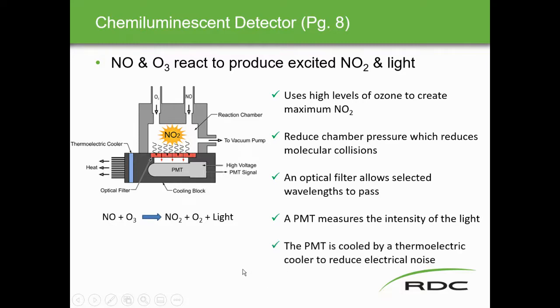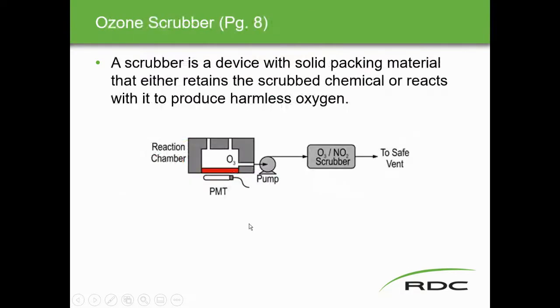The photomultiplying tube is cooled by a thermoelectric cooler to reduce electrical noise. A scrubber is a device with solid packing material that either retains the scrubbed chemicals or reacts with them to produce harmless oxygen. The surplus O3 gets pumped out and scrubbed so that only safe oxygen is vented. The NO2 is also scrubbed before venting.